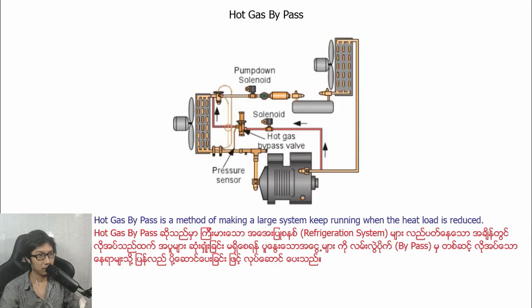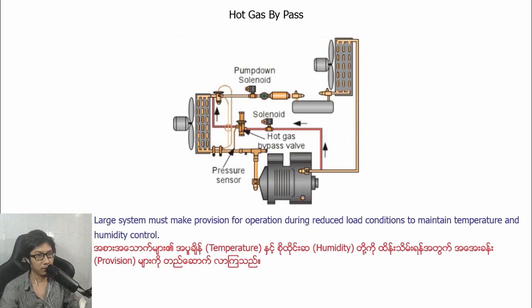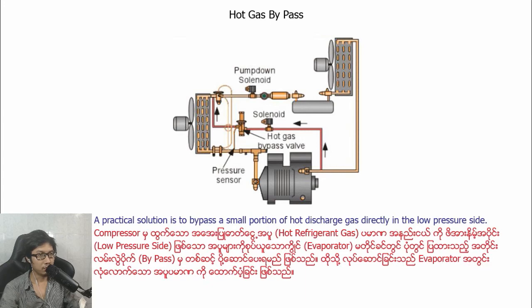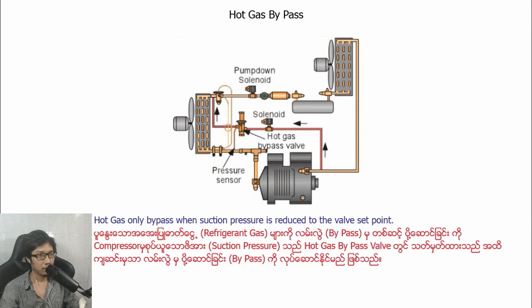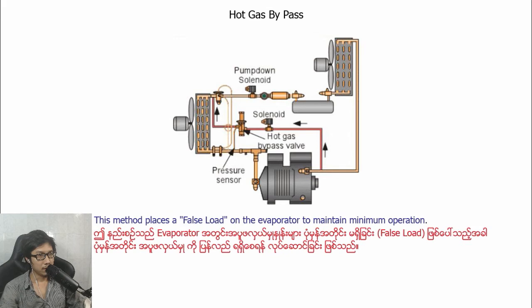Hot gas bypass. Hot gas bypass is a method of making a large system keep running when the heat load is reduced. Large systems must make provision for operation during reduced load conditions to maintain temperature and humidity control. A practical solution is to bypass a small portion of hot discharge gas directly into the low pressure side. Hot gas only bypasses when suction pressure is reduced to the valve setting. This method places a "false load" on the evaporator to maintain minimum operation.